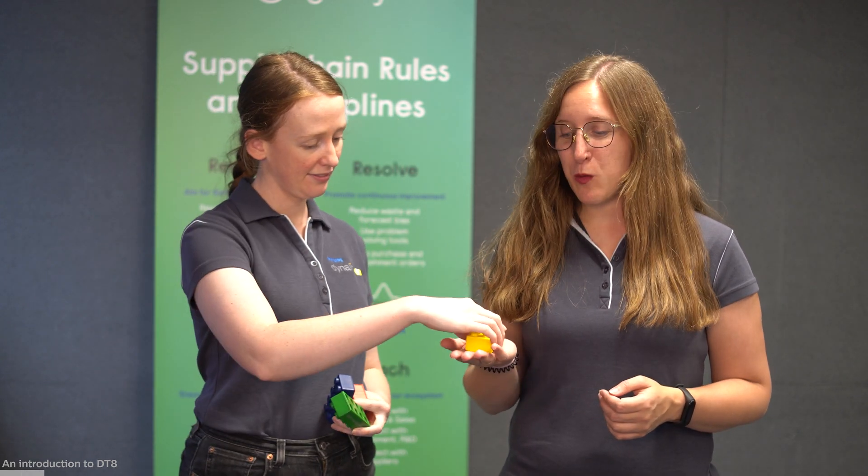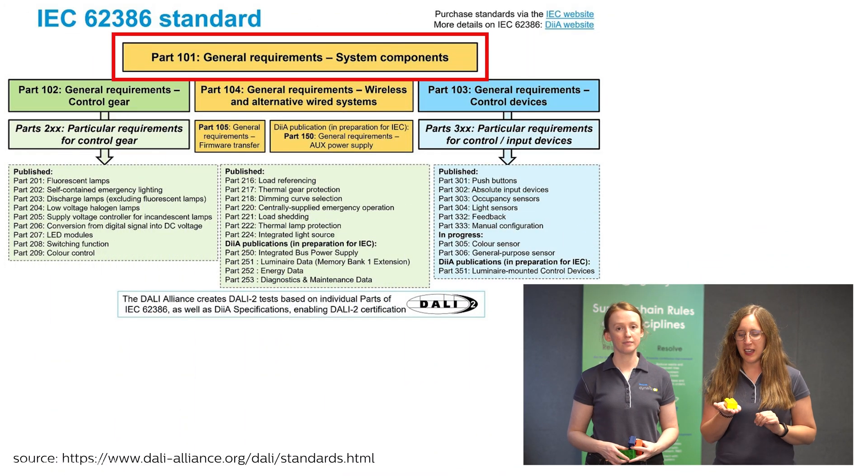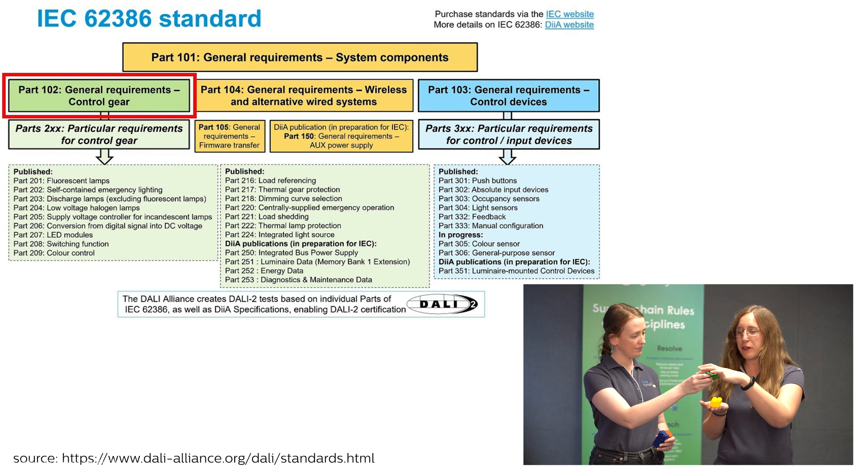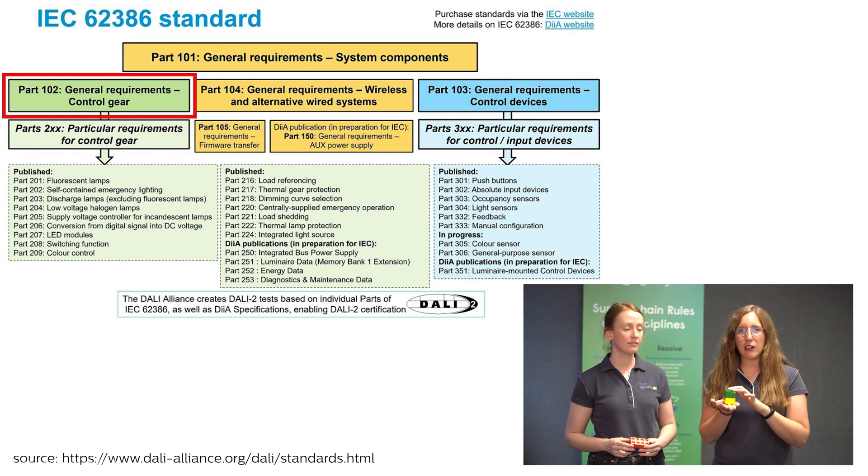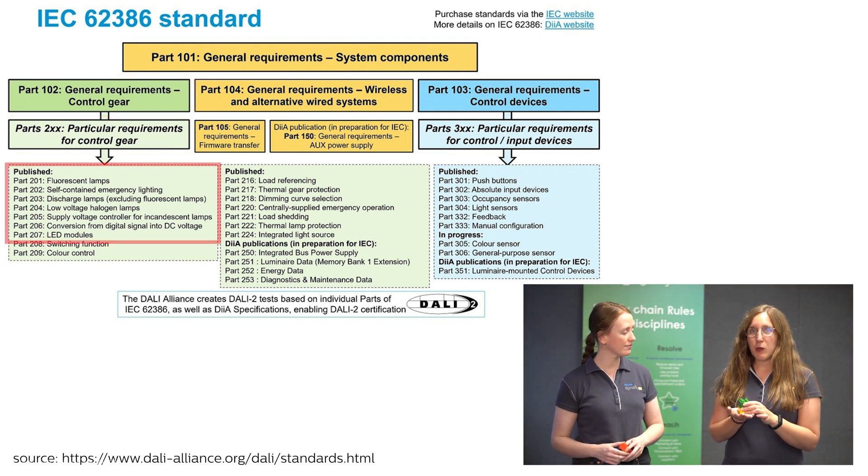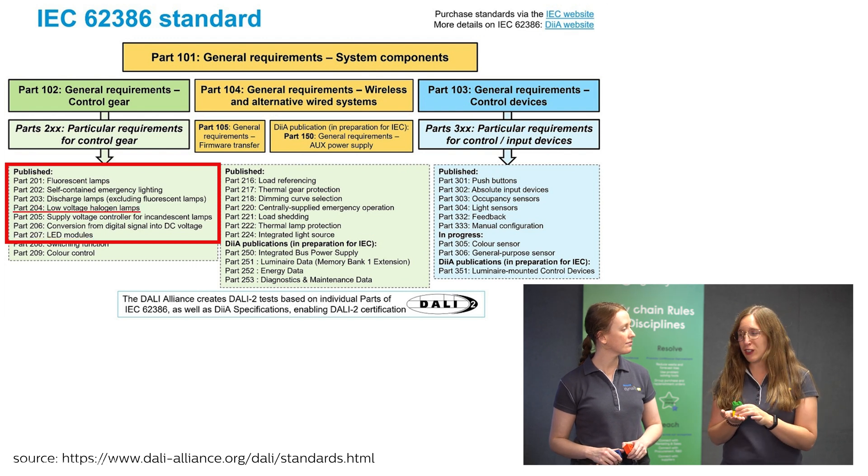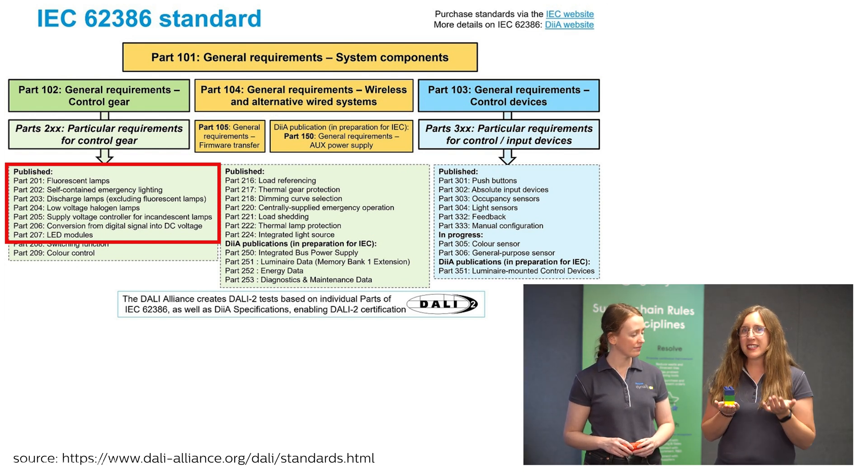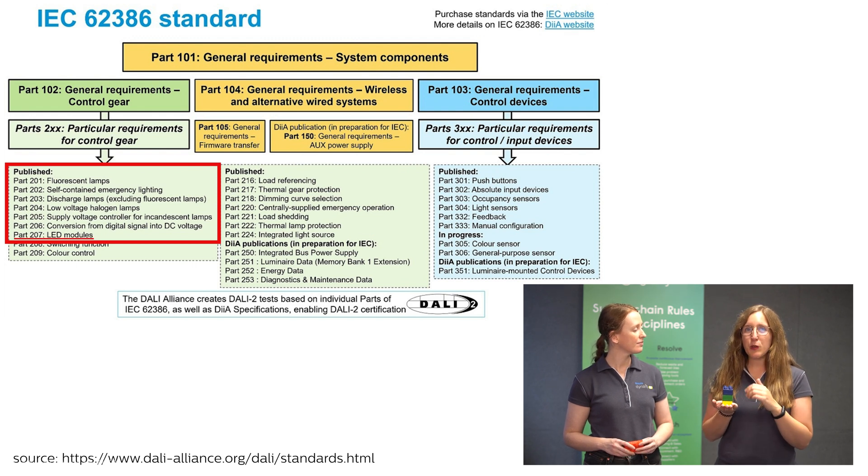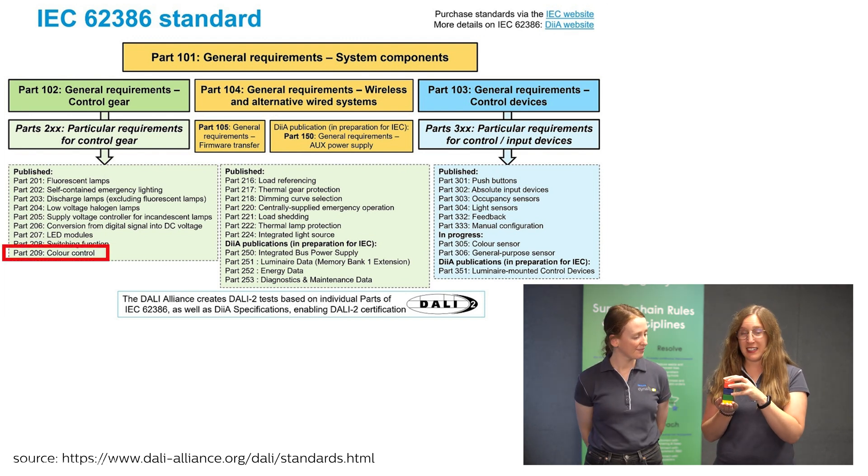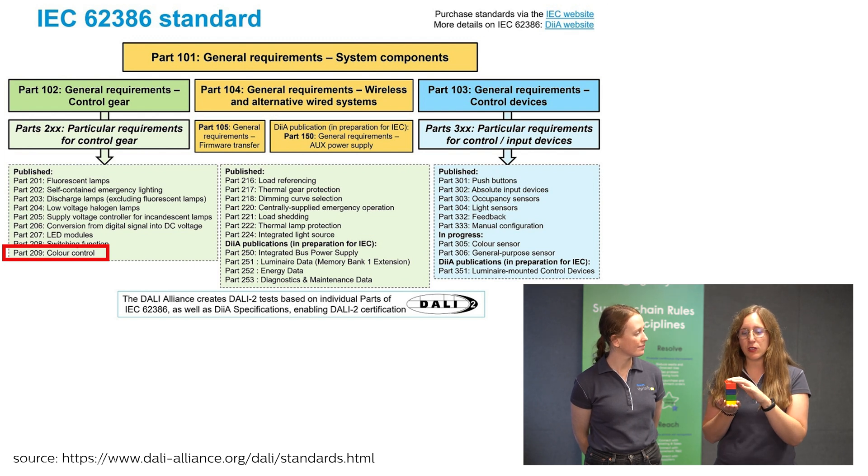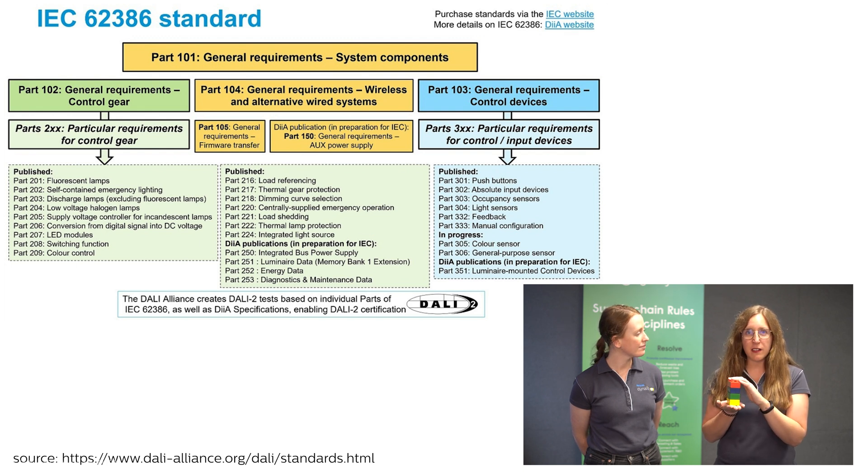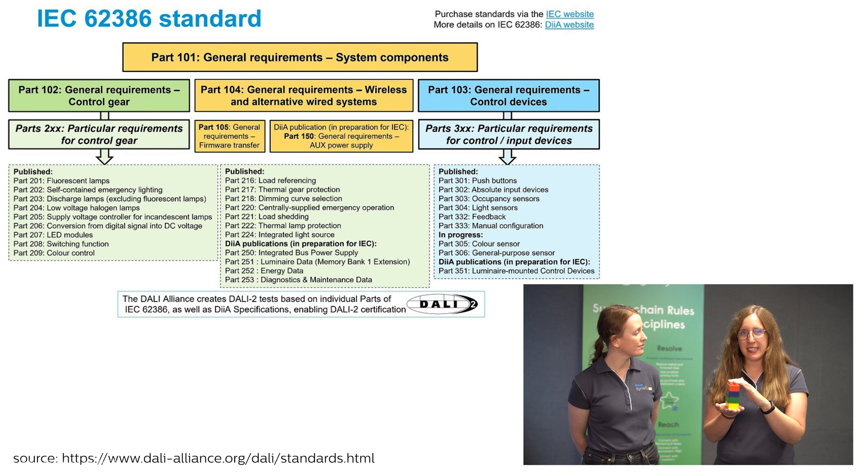So before we move on with DT8 it's important to know that DALI is built on different parts like blocks. First block or part 101 would be the standard requirements for the whole system the whole DALI system including for example the 16 volts or the 250 milliamps. A second block would be needed to define the part 102 which is basically to define the general requirements but in this case for the control gear so for the driver. Now if we want to control a LED module a fluorescent or a halogen lamp we would need a third block like this one here that defines specifically the lamp that we want to control. In this case we will focus on LEDs which makes more sense if we would like to add the fourth module which is this one here which is exactly DT8 and defines the general requirements for color control. So all these blocks are independent they do not overlap and contradict themselves but together they form the module that we want to control including the lamp and the driver in the DALI system.